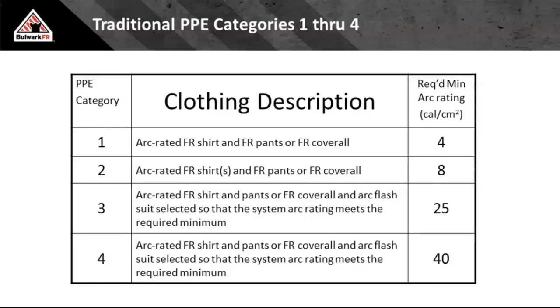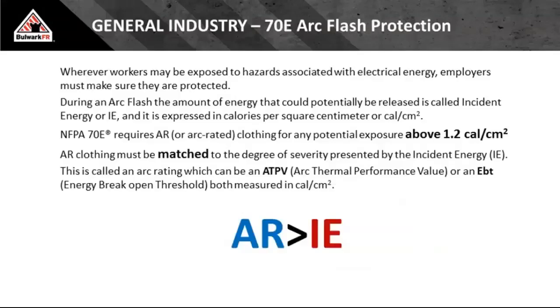Or if you're using the simplified two-step approach at your facility, you're using 8 cals or greater all day, every day, and then for anything over that, you're going into a 40-cal flash suit to work on that 11-cal piece of equipment. That's why it's so key to know what your incident energies are, because you can dress far lighter in many cases if you know what the incident energy is, as opposed to rounding up utilizing the Cat method. So just something to think about. We do all that discussion, these last 4 slides, to give you this information.